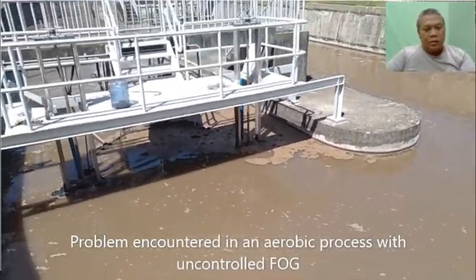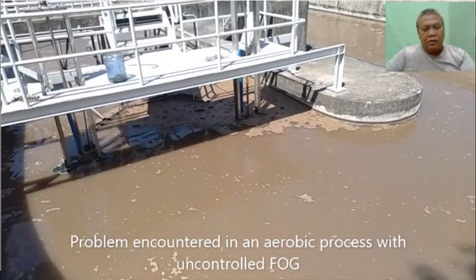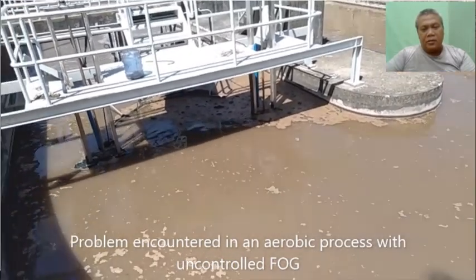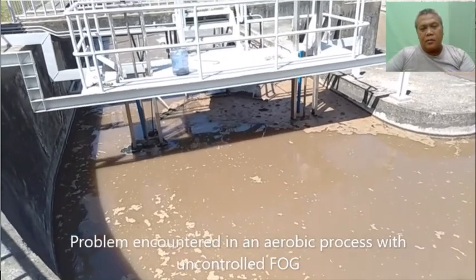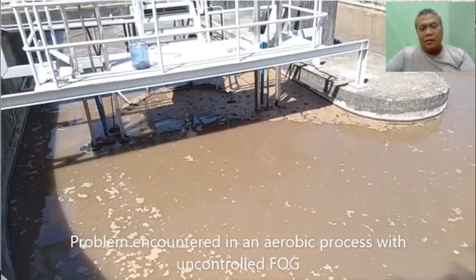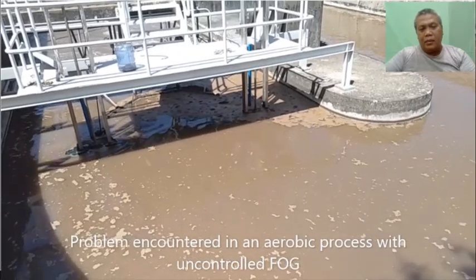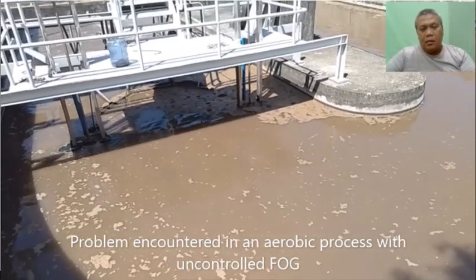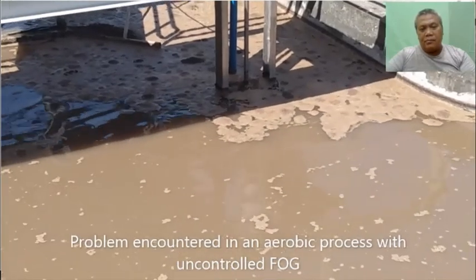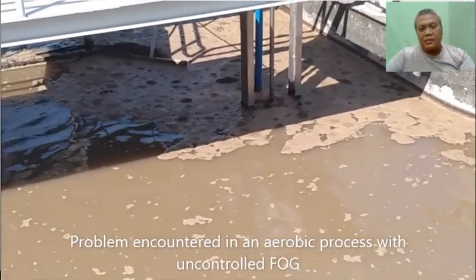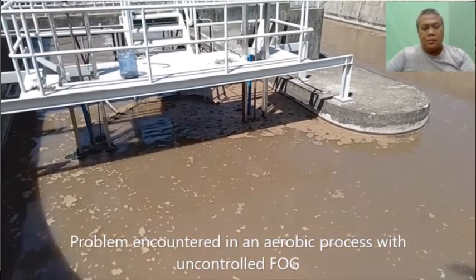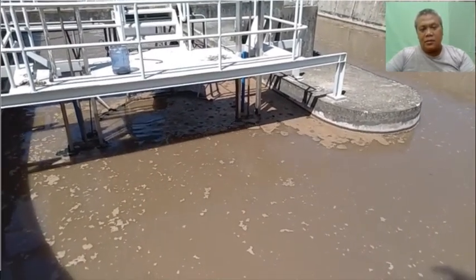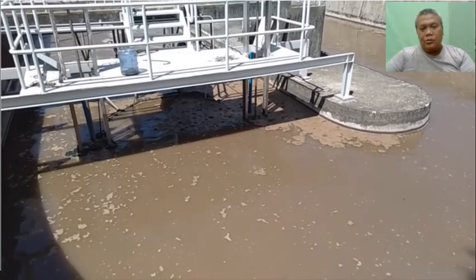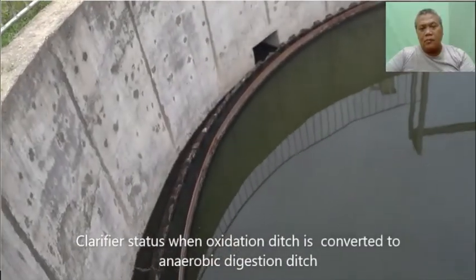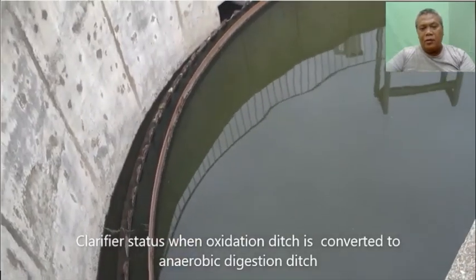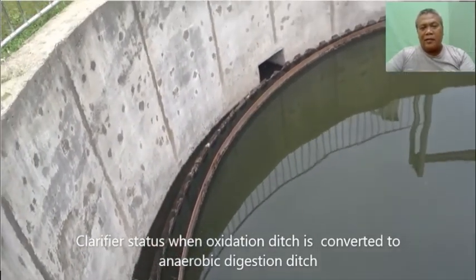Now you will see that there is a lot of fats and grease in the oxidation ditch. This is a problem. As you can see, the clarifier is already filled up with the floating sludge or scum that is being washed out from this aeration basin or oxidation ditch. And we'll show you the clarifier when it is already being used as part of the BNR.